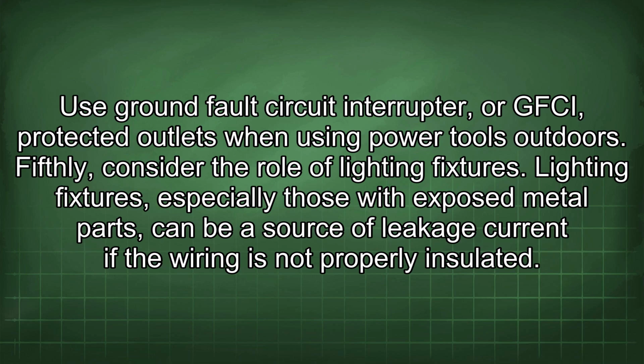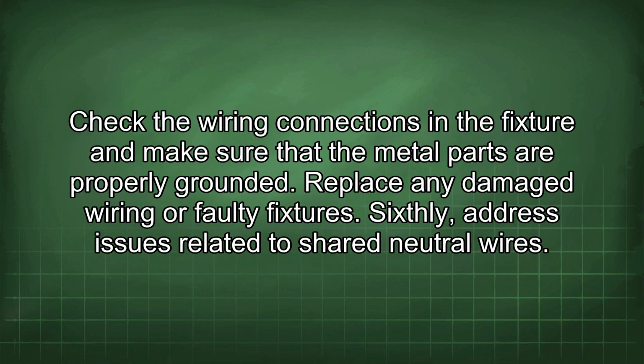Fifthly, consider the role of lighting fixtures. Lighting fixtures, especially those with exposed metal parts, can be a source of leakage current if the wiring is not properly insulated. Check the wiring connections in the fixture and make sure that the metal parts are properly grounded. Replace any damaged wiring or faulty fixtures.